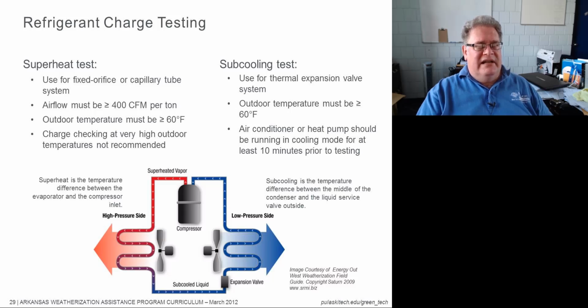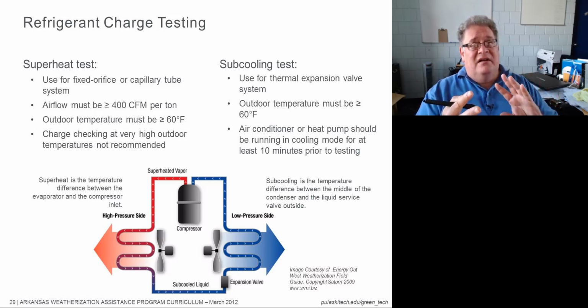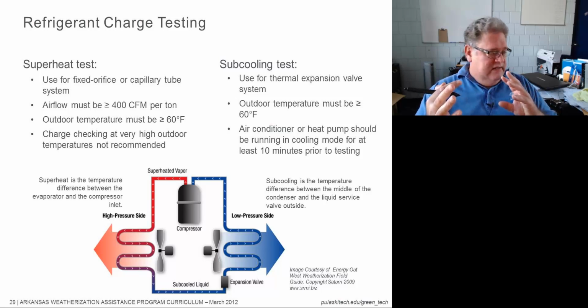You're not going to do this in a heating climate, all right? And generally, you're going to be an HVAC contractor. But as a quality control inspector, you should understand whether or not this test is being done at the proper time and under the right conditions. And there are different tests depending on what the valve configuration is.